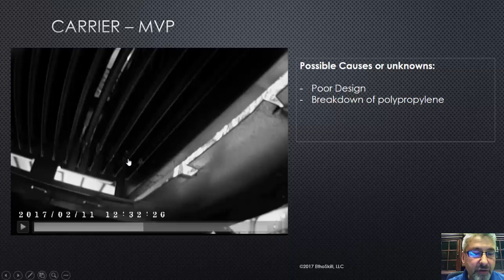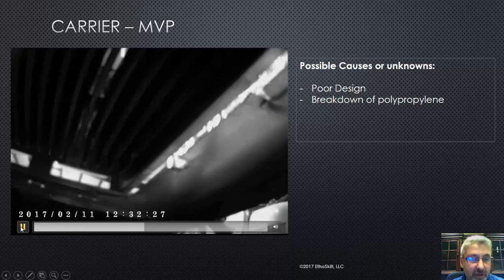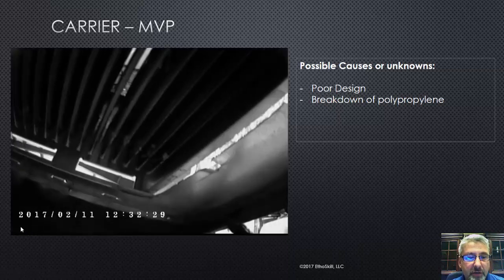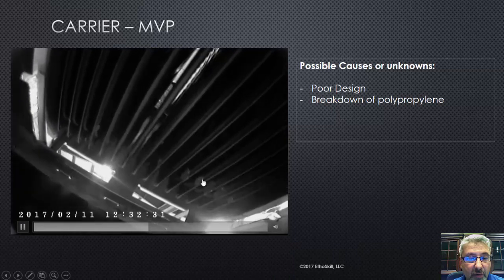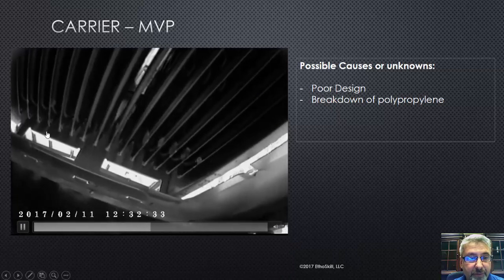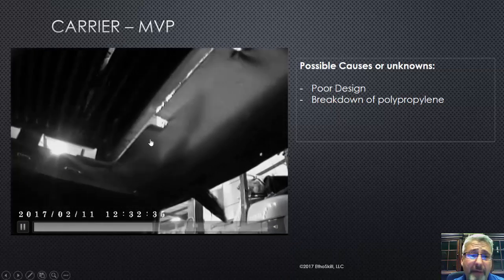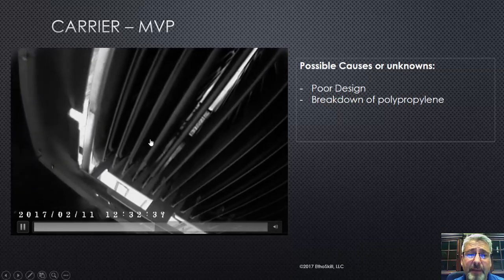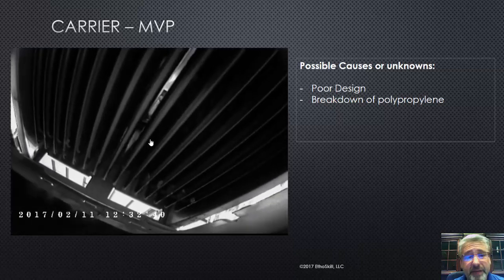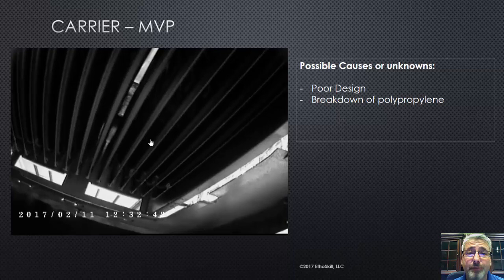So this is the corrosion, and out in the video there's a better shot of that. So let's just go ahead, and I may even fast forward to accelerate. Oh, there you can see it real well, the corrosion. And that's a problem. You don't want that. If your furnace has that, that's a problem. That secondary has failed, and it's because of the polypropylene that's breaking down.